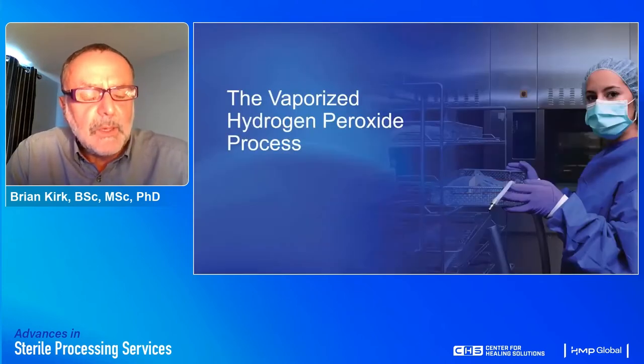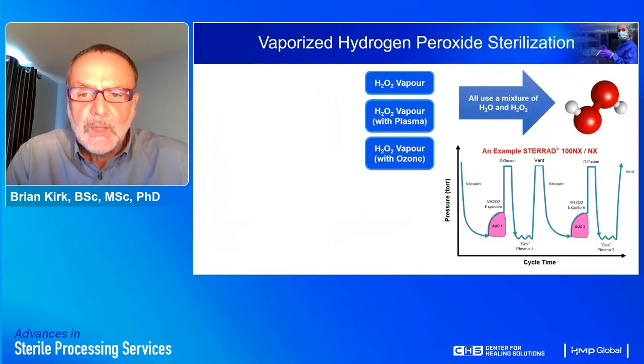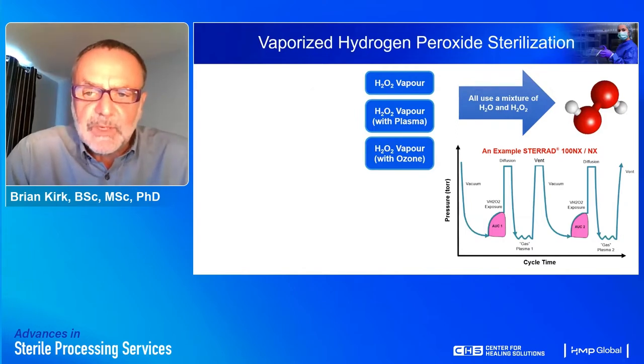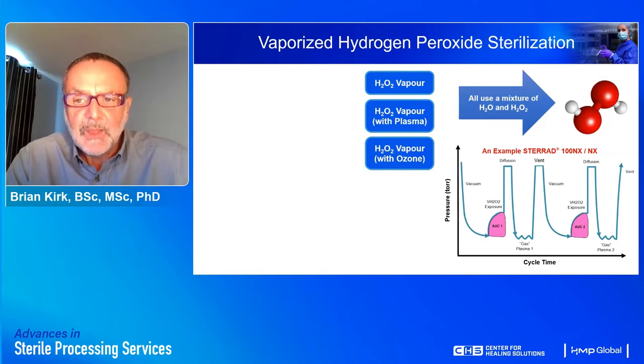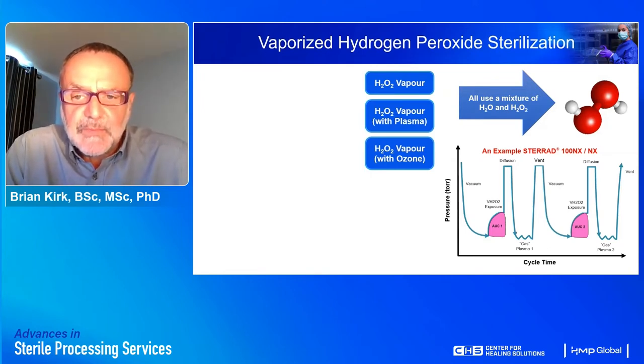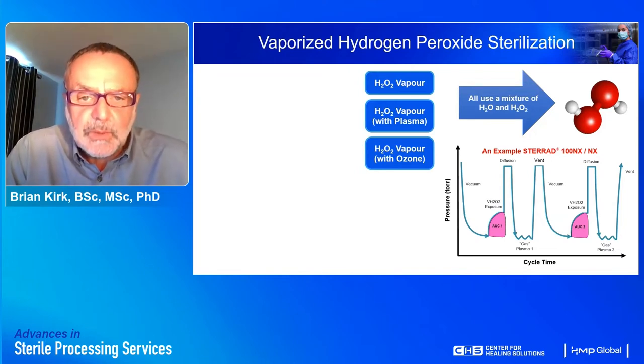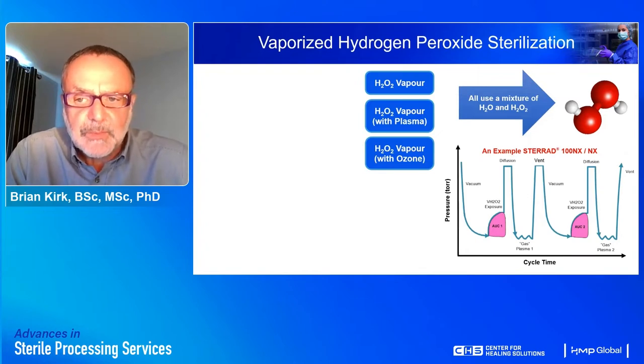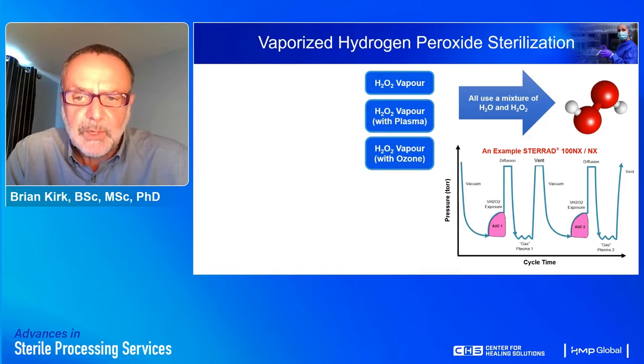The vaporized hydrogen peroxide process is the most recent process for sterilization of packaged heat-sensitive medical devices. There are no specific international or European standards for hydrogen peroxide processes, so all of them are different, though local guidance documents exist in some countries and standards are currently in preparation.